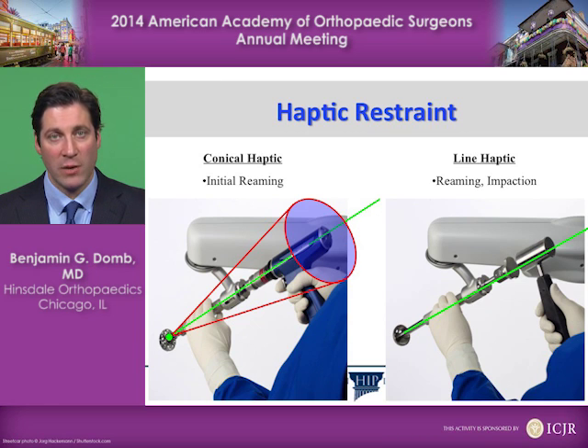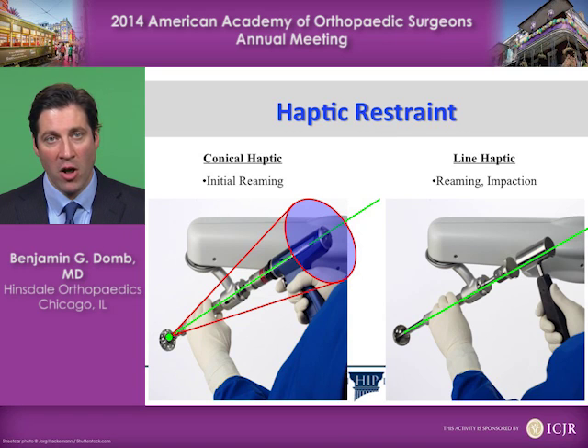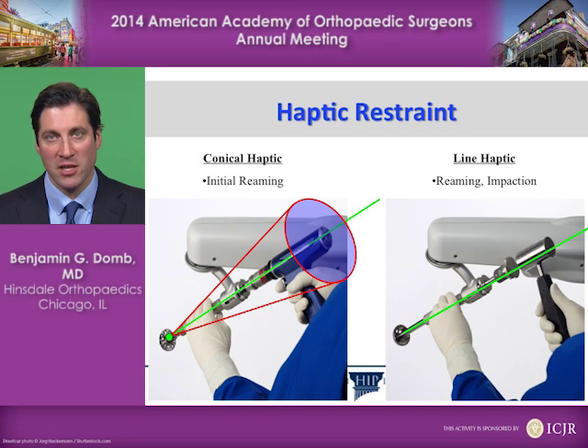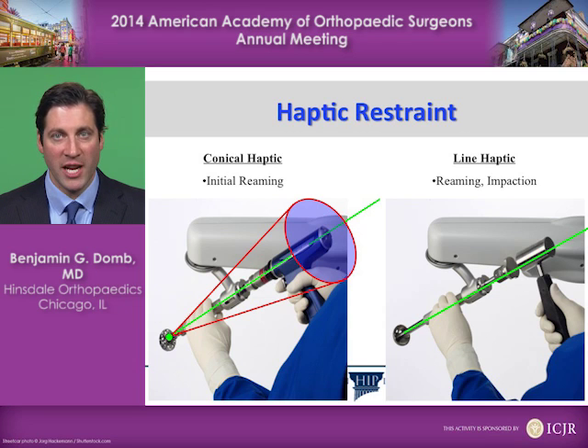The haptic restraints use conical haptics for the reaming. We can actually ream from a variety of different approaches, but all the while it keeps the basket in the desired location in space. When we go to the impaction of the cup, it switches over to linear haptics, keeping us in the direct line of approach that will produce the version and inclination that we've templated.